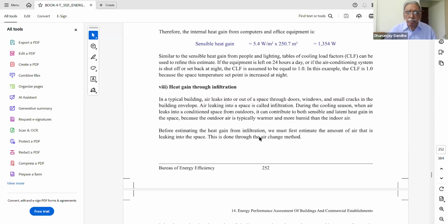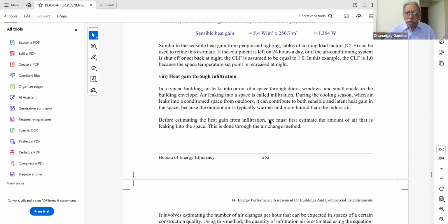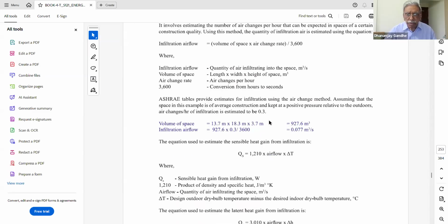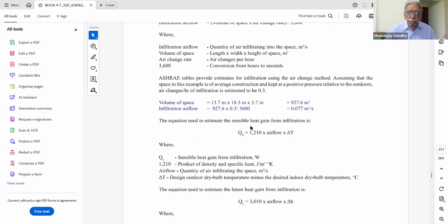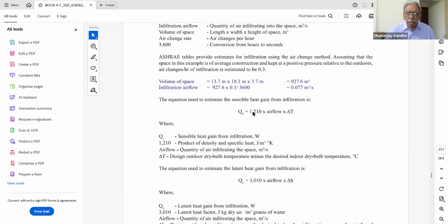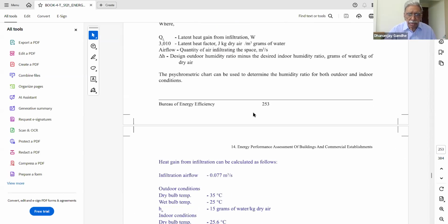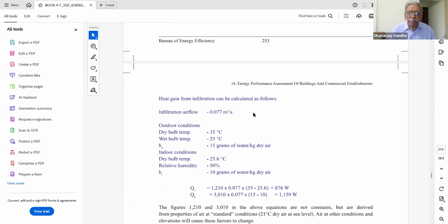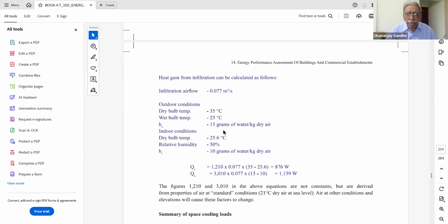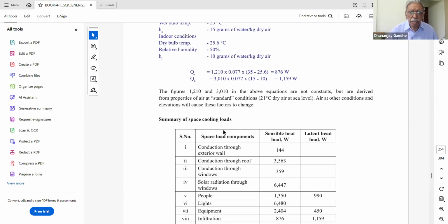Then there are also calculations to be made for heat gain through infiltration. So there are formulae given here. They are the standard formulae which need to be used. So figures of area, volume of the space, and airflow are given here, so this can be calculated. So you can calculate the heat gain from the infiltrated air that leaks in because of the gaps in the walls and also in the roof, or maybe also the windows. So infiltration airflow calculations are mentioned over here.